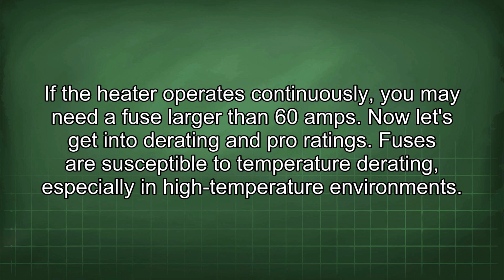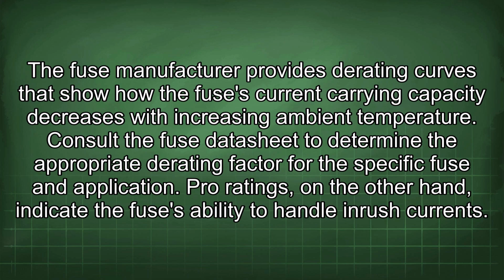Now let's get into derating and pro-ratings. Fuses are susceptible to temperature derating, especially in high-temperature environments. The fuse manufacturer provides derating curves that show how the fuse's current carrying capacity decreases with increasing ambient temperature. Consult the fuse datasheet to determine the appropriate derating factor for the specific fuse and application.